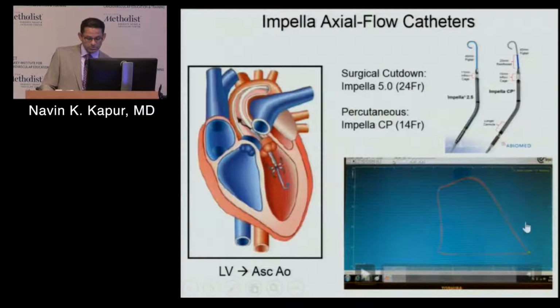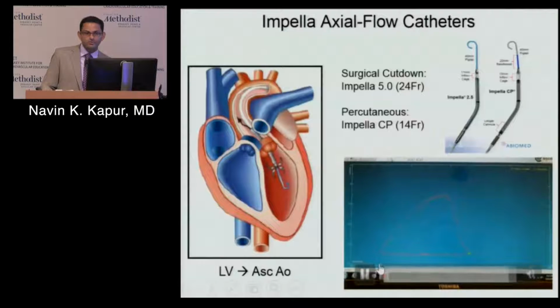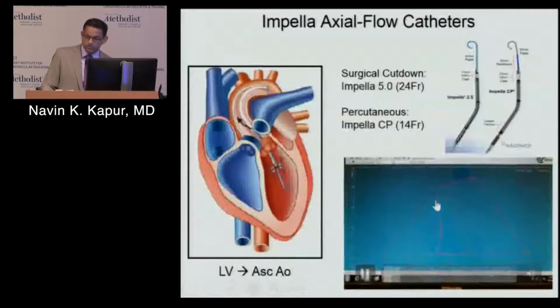volume this device is going to give us. So here's the pressure-volume loop at baseline, with the device sitting across the aortic valve, so you get this skewed upstroke here. This is volume, this is pressure. We activate the 5.0 device, and very consistently what we were seeing was essentially a melting away of that pressure-volume loop. What we wanted to see is what we were visualizing, which is this drop in pressure and this drop in volume simultaneously.